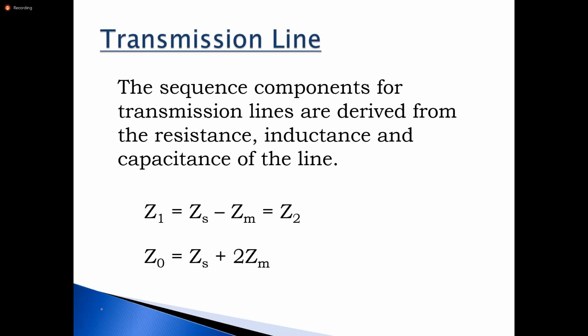So in effect, what we're saying here is that your positive and negative sequence impedances are smaller than your zero sequence impedance. Keep that in the back of your mind. If you see values that are not true to what we have here, because if it's the same line, the self-impedance and the mutual impedance must be the same whether we are calculating the zero sequence or the positive sequence impedances. And if I give you Z1, it means that you also have Z2.